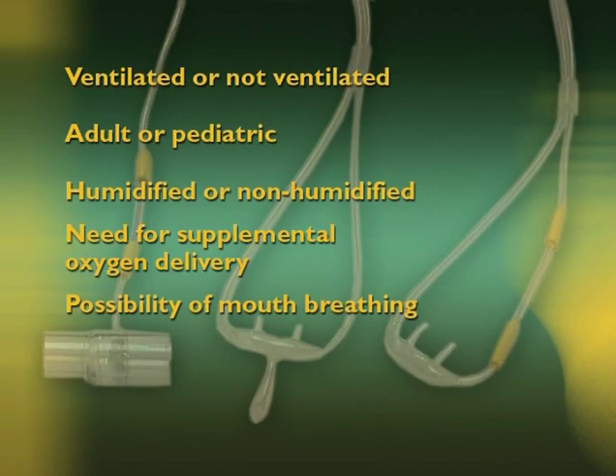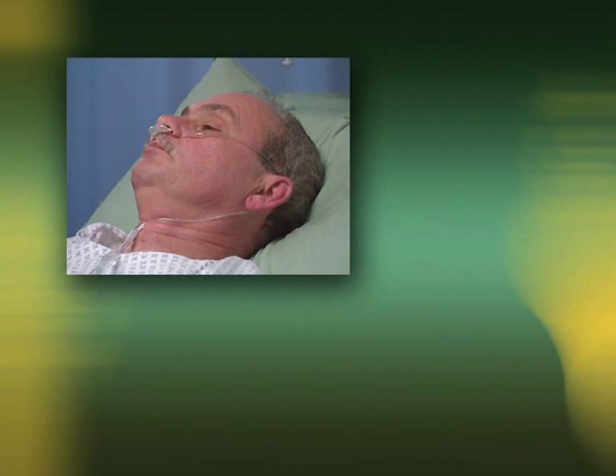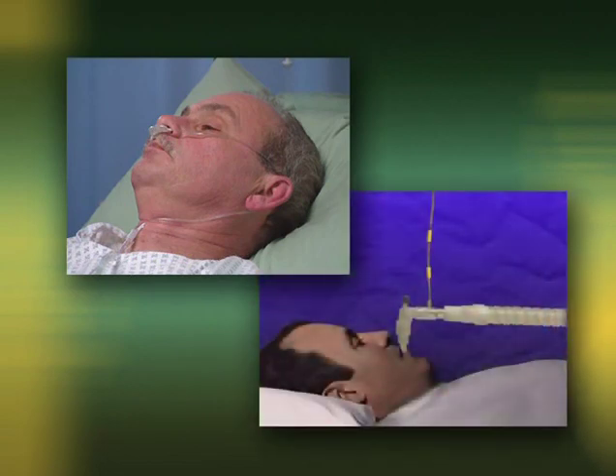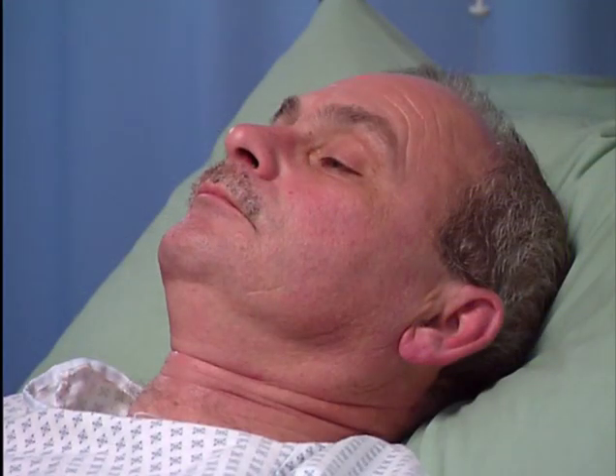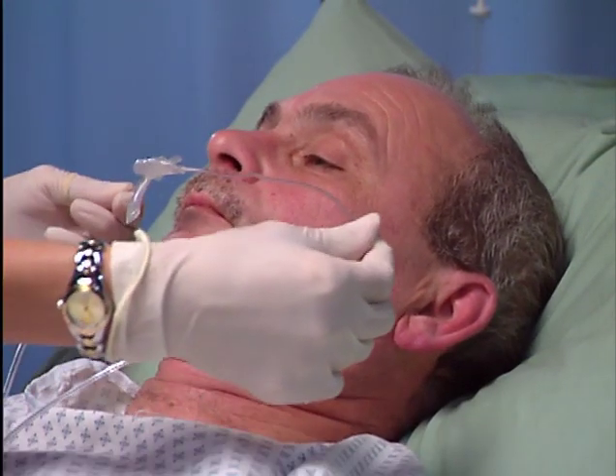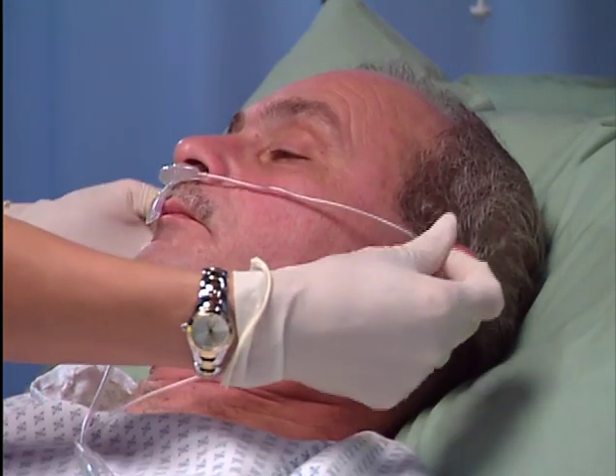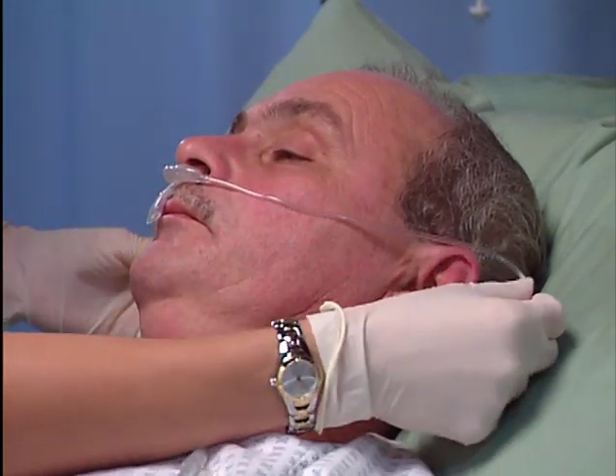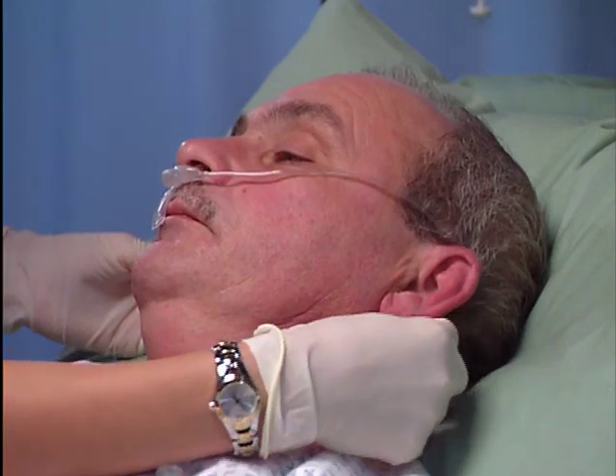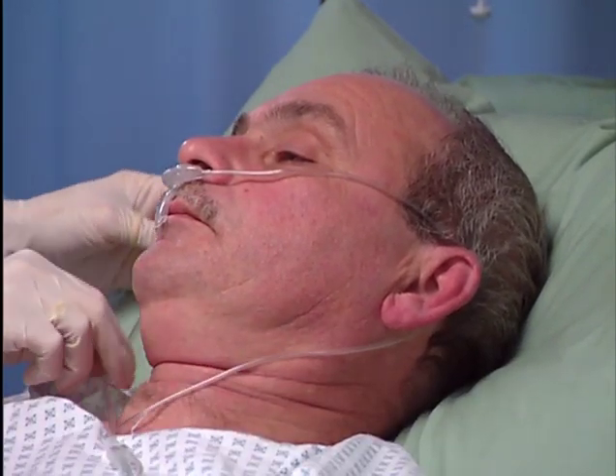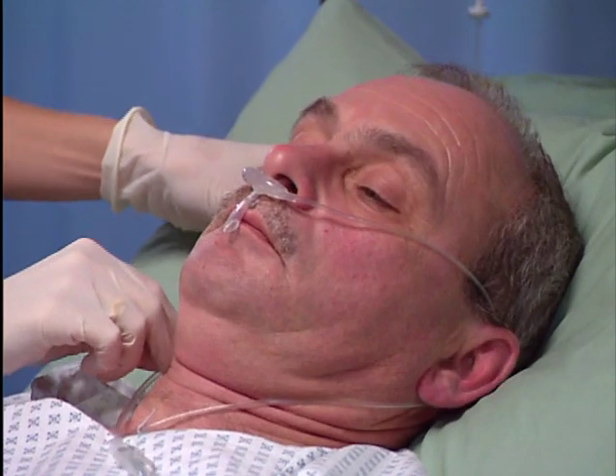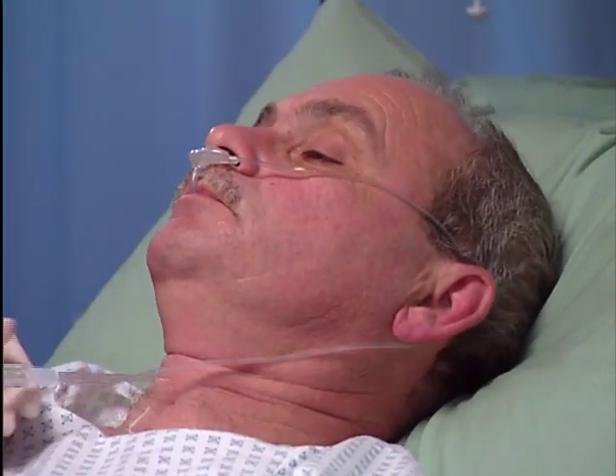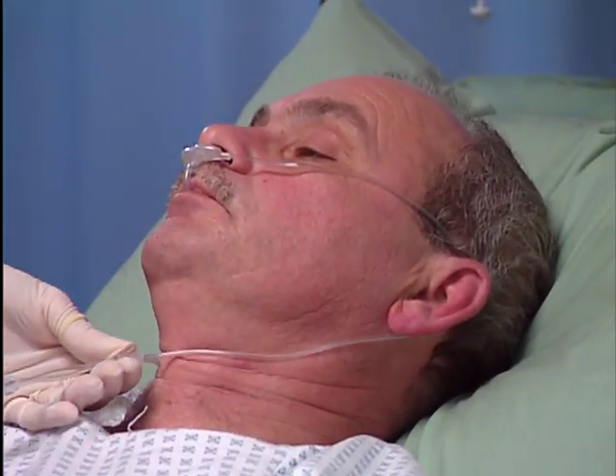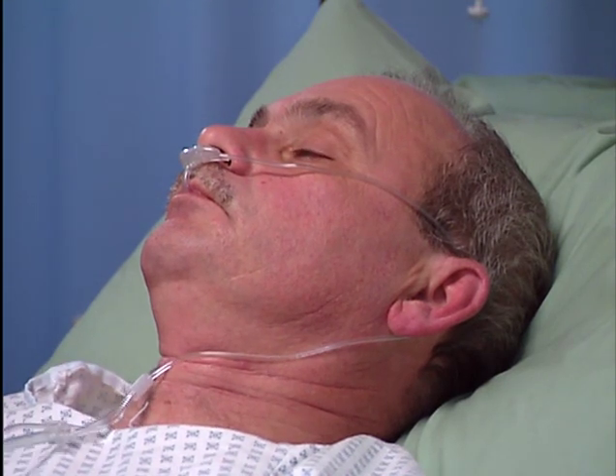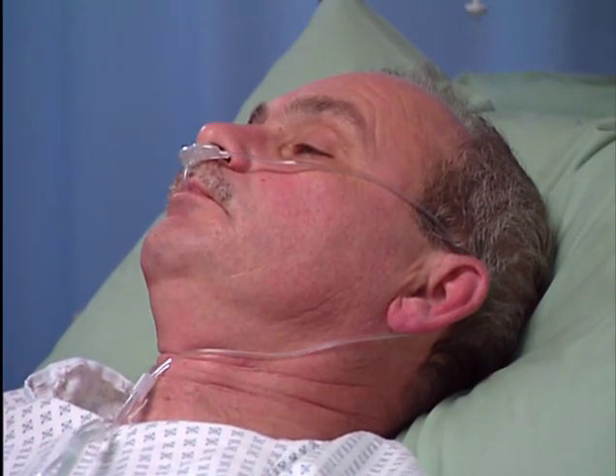There are 2 filter line options in microstream monitoring: non-intubated nasal cannula and a filter line with an airway adapter. When using the nasal filter line, check that both nostrils are clear. Position the nasal filter line on the face by inserting the filter line tips into the nostrils. Pass the filter line tubing over the ears. Slide the sleeve up the tubing towards the neck for a comfortable fit under the chin. Check the positioning of the filter line to ensure proper detection during monitoring.